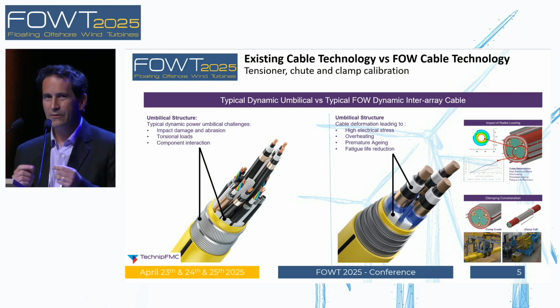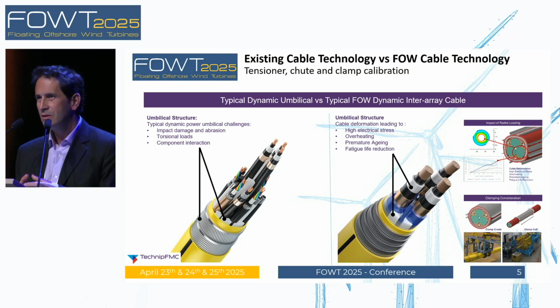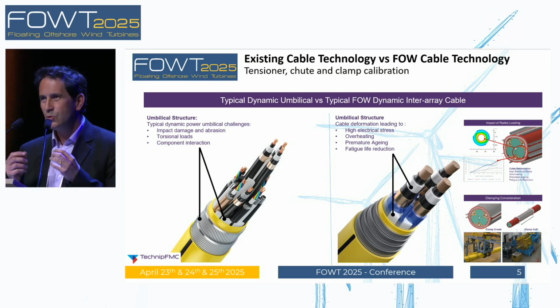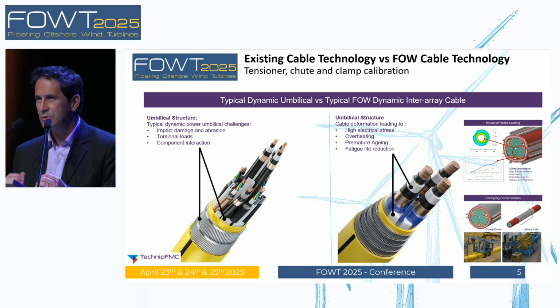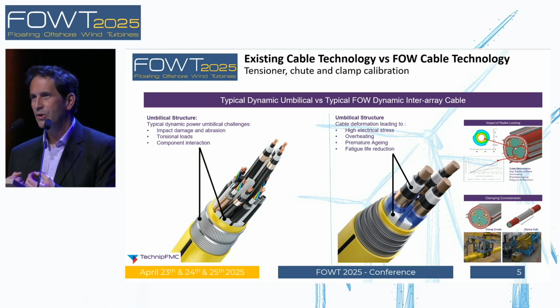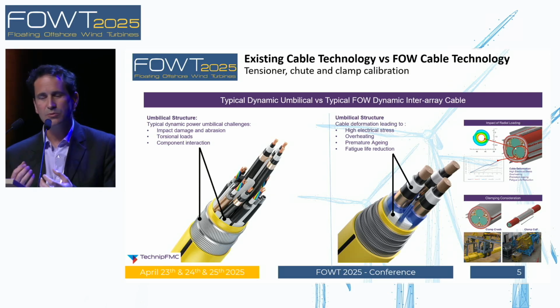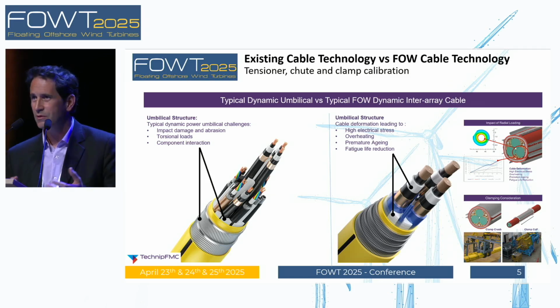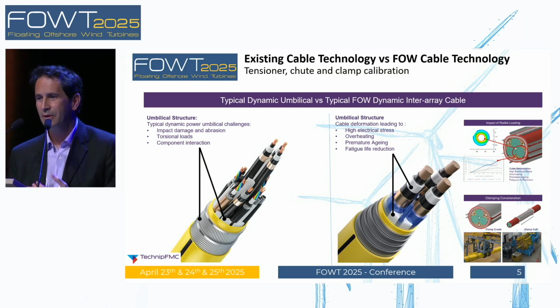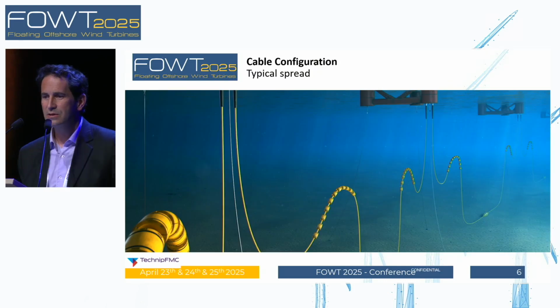And the key here, if there is a message to the presentation, is that when designing these dynamic cables, we need to be fully aware of the failure modes. We need to analyze the failure modes and address them. Because these cables are so thick that they will generate heat, and the heat will generate premature aging of different sheaths and different materials within the cable. So this premature aging needs to be taken into account in the design. You might have a cable that runs for several years without noticing that the aging is faster than planned, right? So that's what's illustrated here in terms of installation.